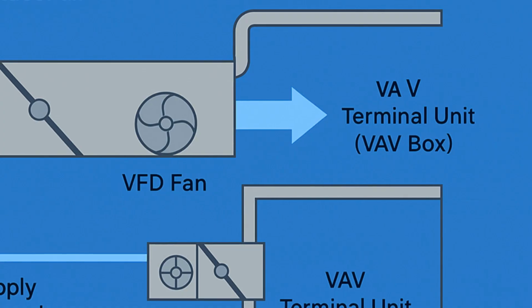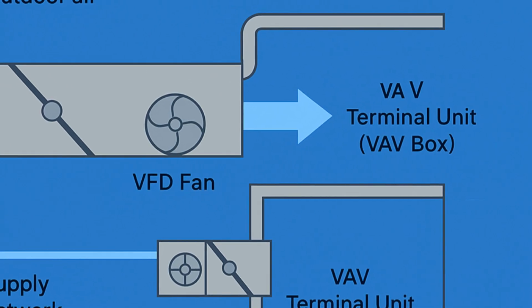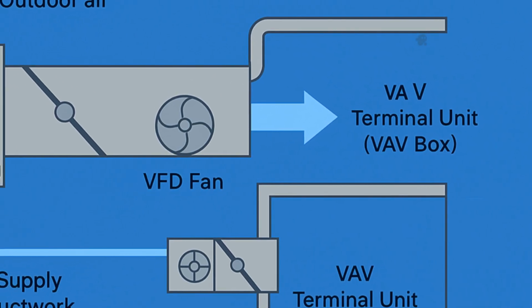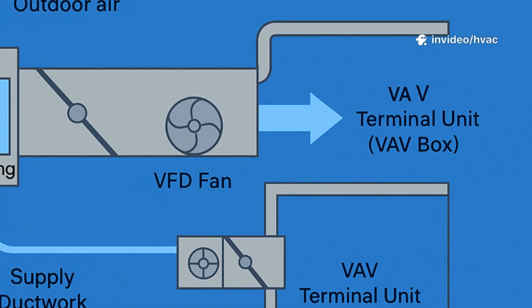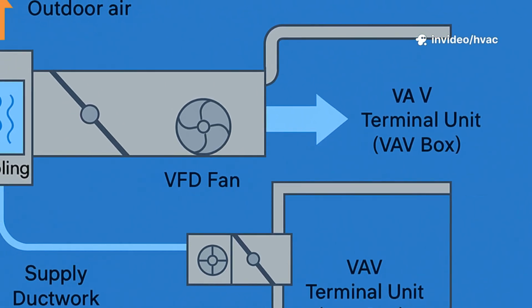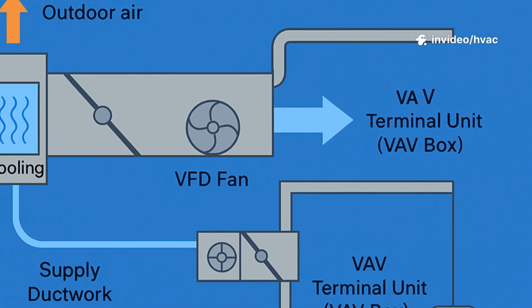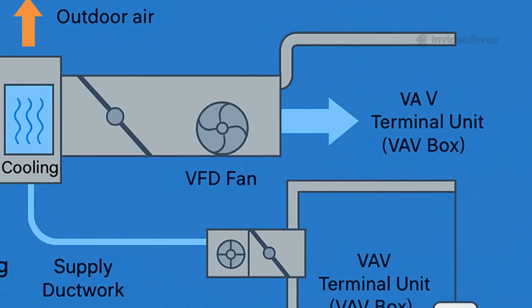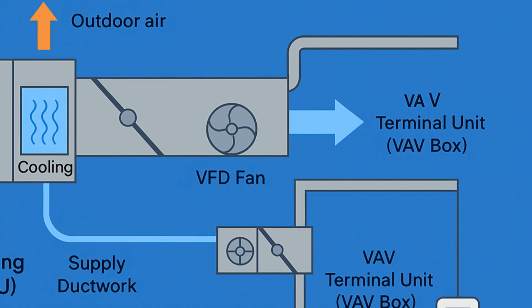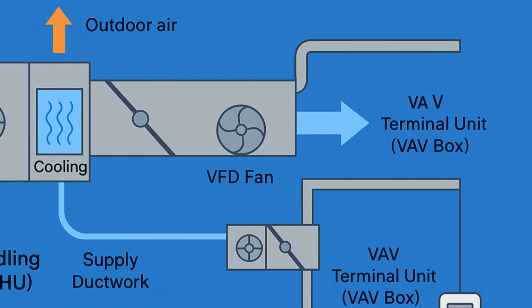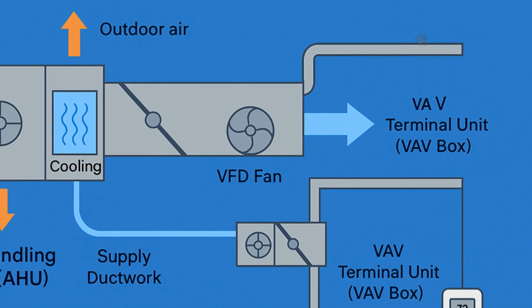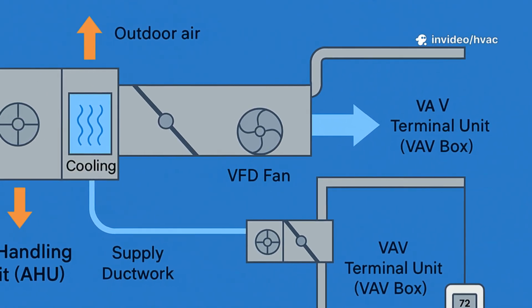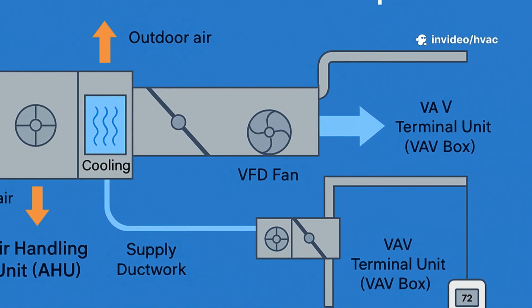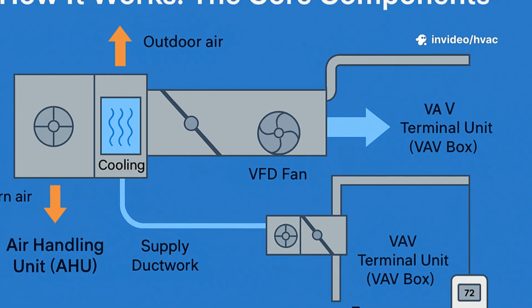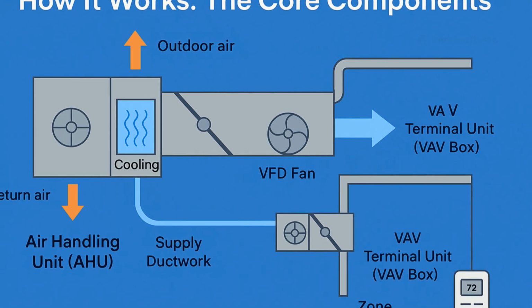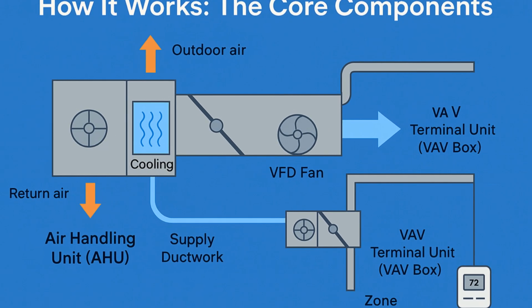What's something people don't know about VAV terminal units and thermostats? Each VAV box modulates airflow within a specific range, typically defined by design parameters: a maximum cooling CFM to meet peak loads, and a minimum CFM, which ensures ventilation compliance and prevents stagnant air. For cooling-only configurations, that minimum might range from 20–30% of the box's design airflow. The box never fully closes. It always maintains at least this baseline airflow to support indoor air quality.